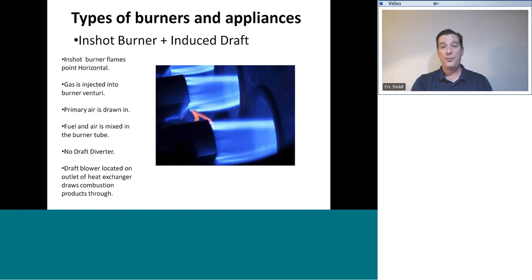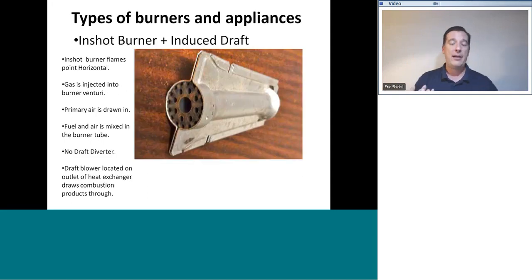products through. Our natural draft had to be vertical because of that natural suction, but with our in-shot induced draft appliances, the flue products move horizontally and they will serpentine back and forth through the heat exchanger. We've got to have a fan to pull them through.